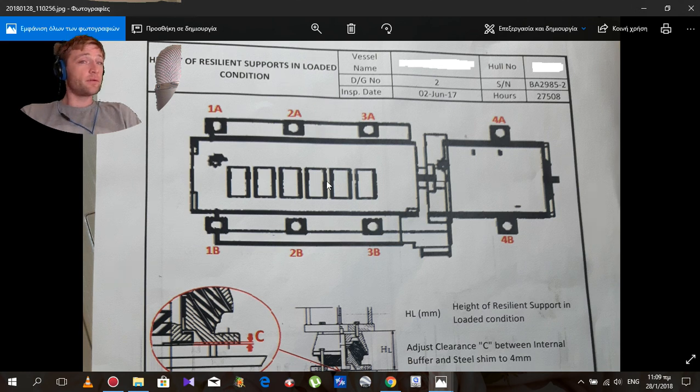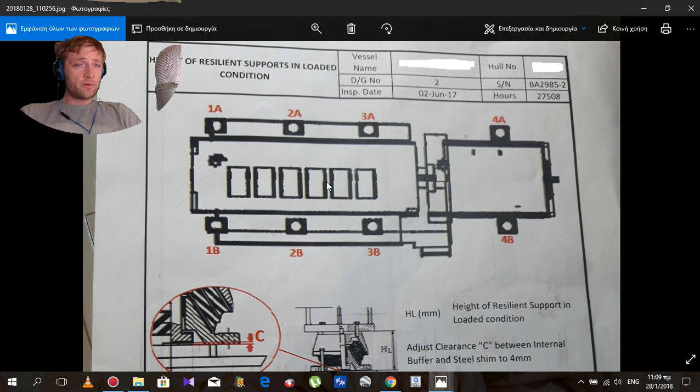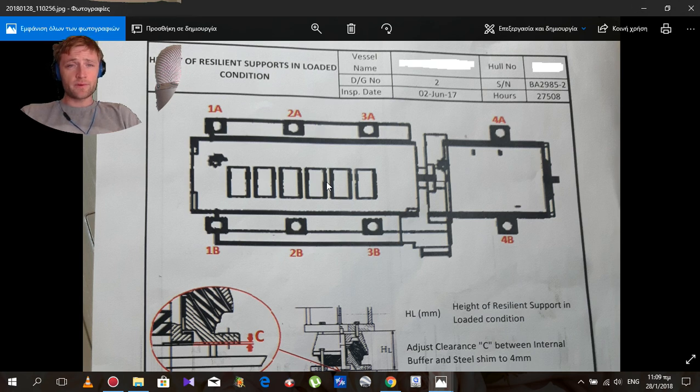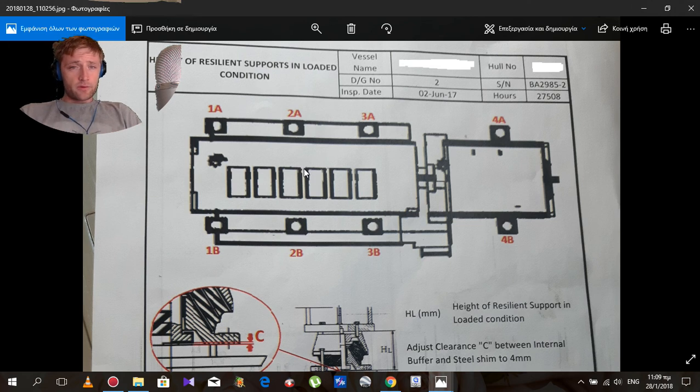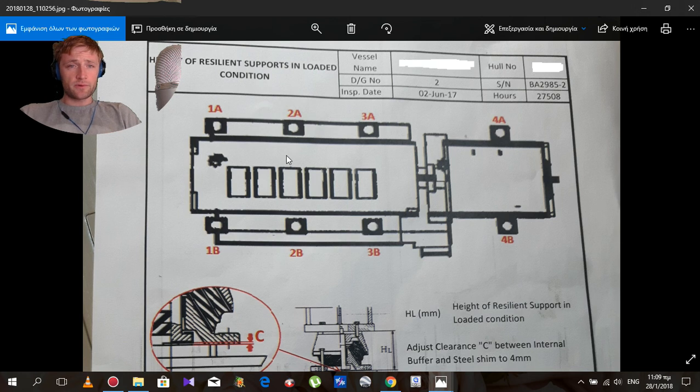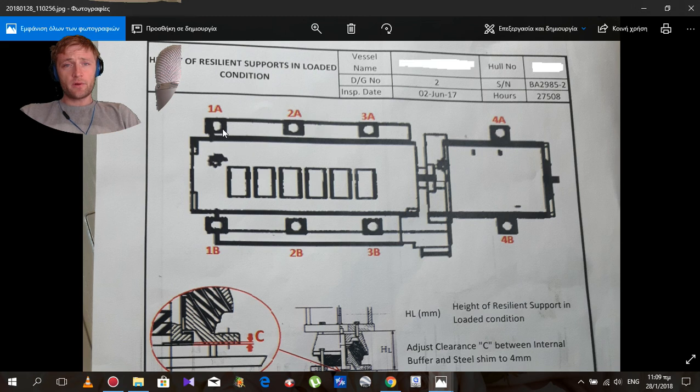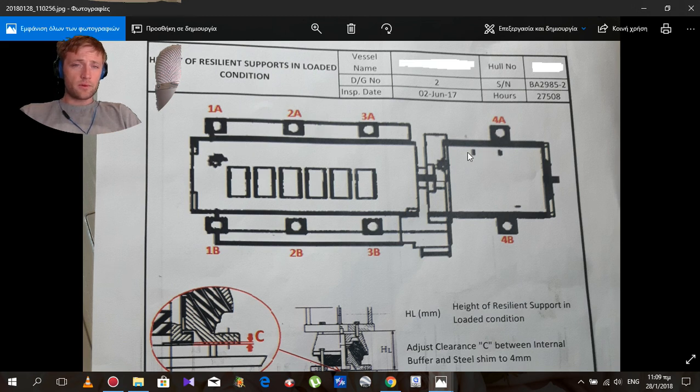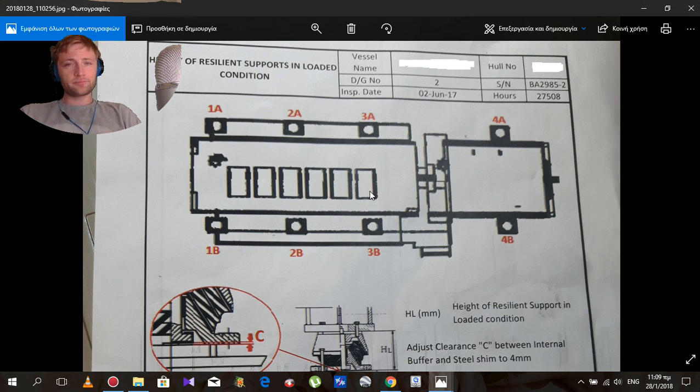As you understand and have seen now, we will talk about the height of resilient supports in loaded condition. As you know, diesel generators have some supports called resilient, and as we see here, we have eight pieces on a six-cylinder diesel generator engine.